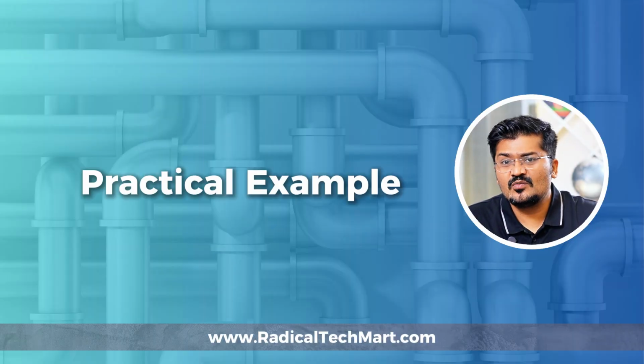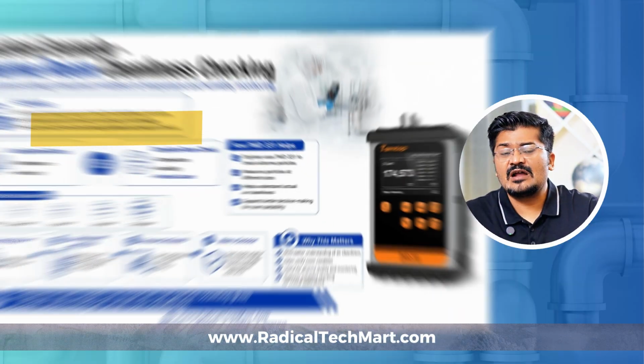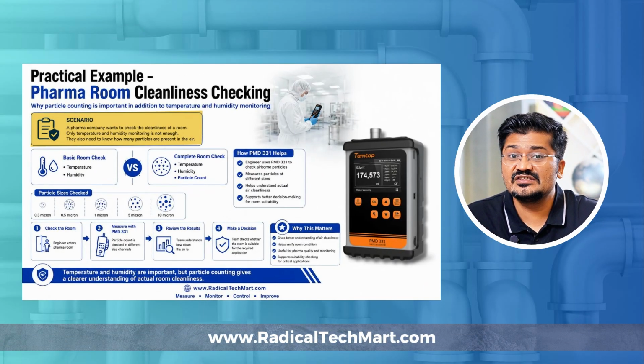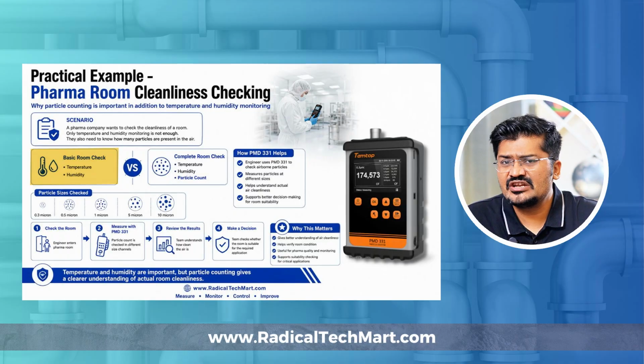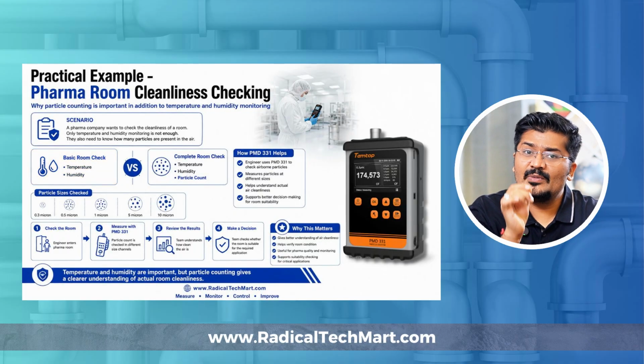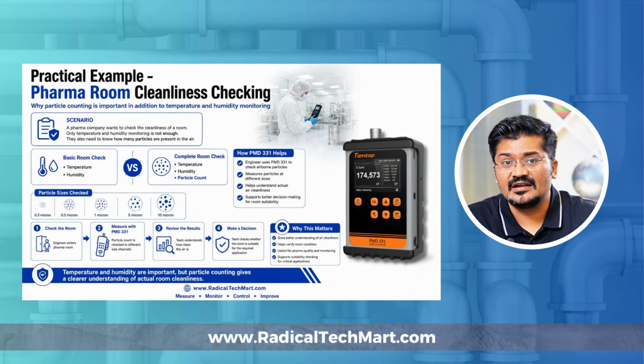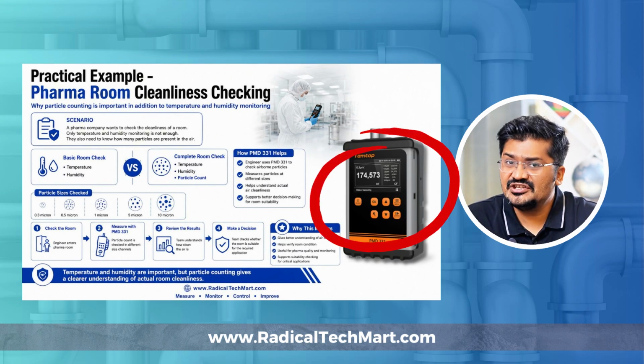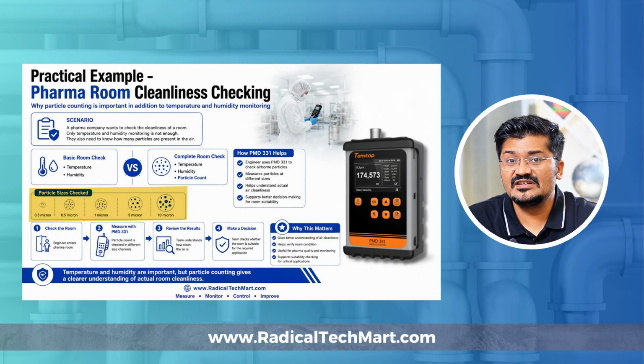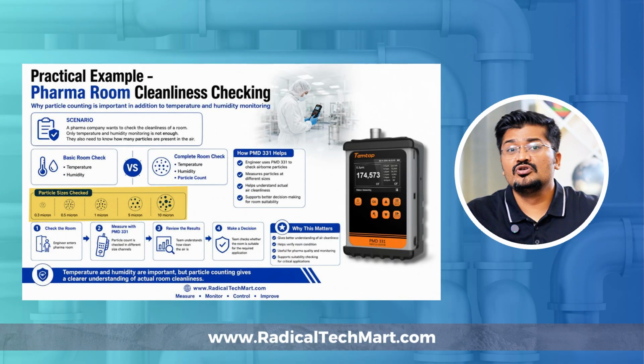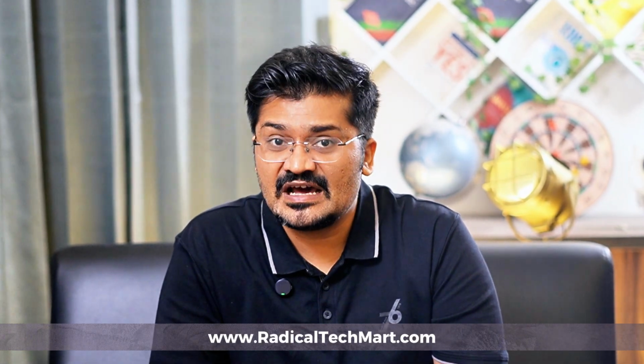So let's take one practical example. Suppose a pharma company wants to check the cleanliness of a room. Only temperature and humidity checking is not enough. They need to know how many particles are present in the air. Using PMD 331, the engineer can check particles at different sizes like 0.3 micron to 10 micron. This gives a better understanding of air cleanliness, and based on this data, the team can check whether the area is suitable for the required application or not.